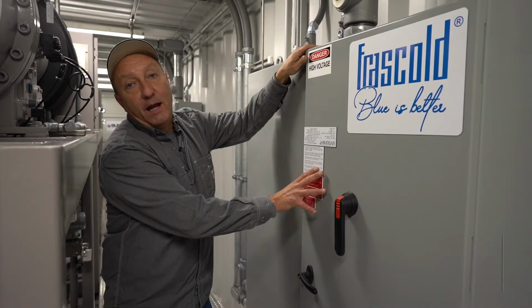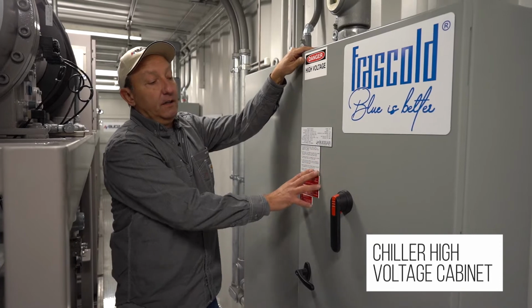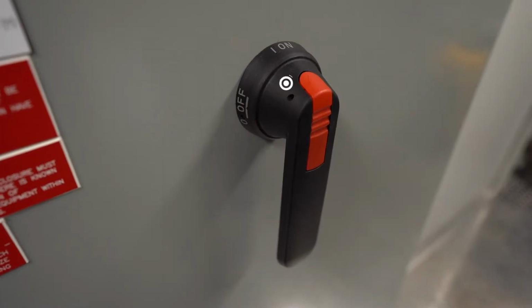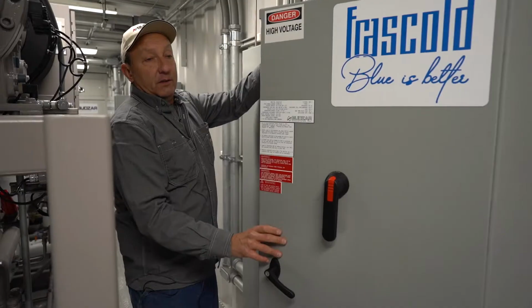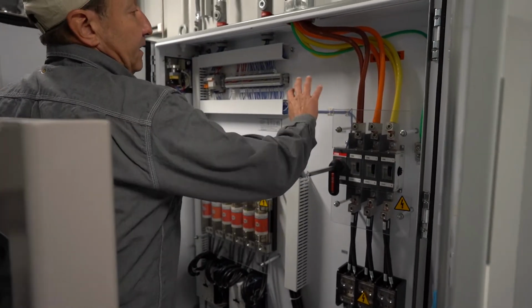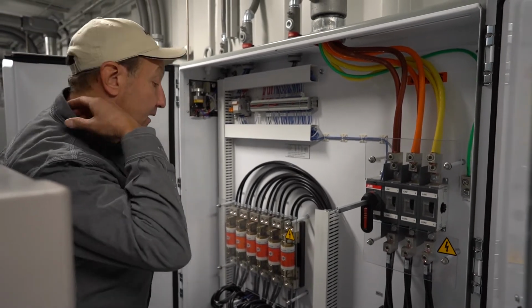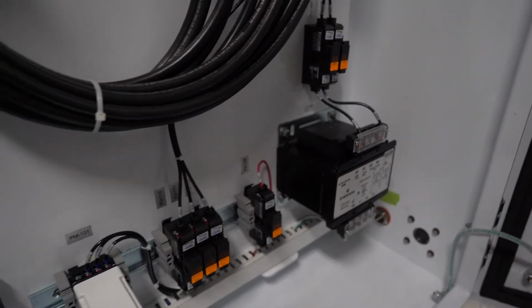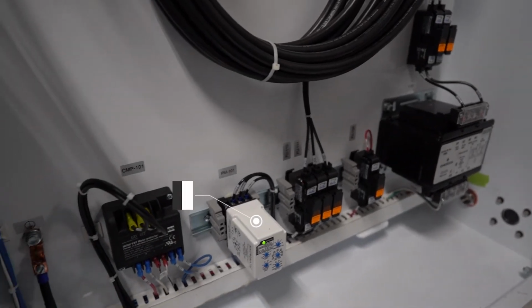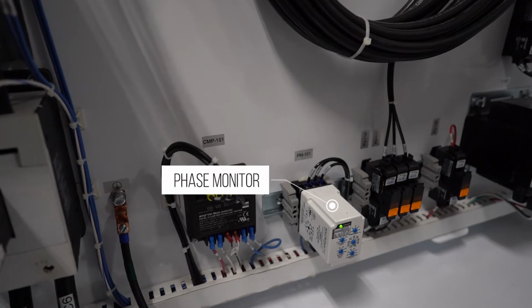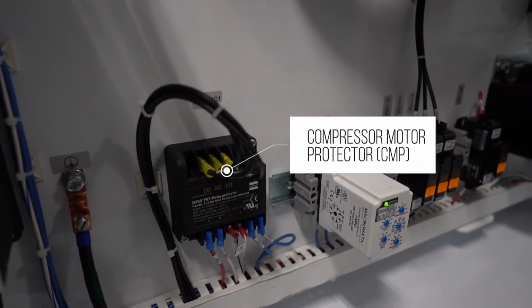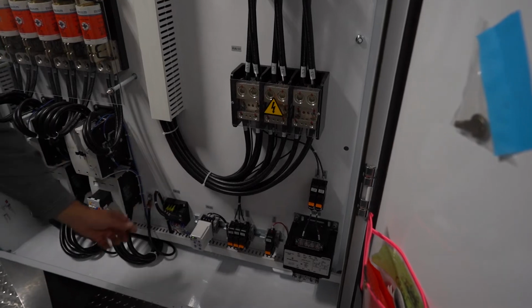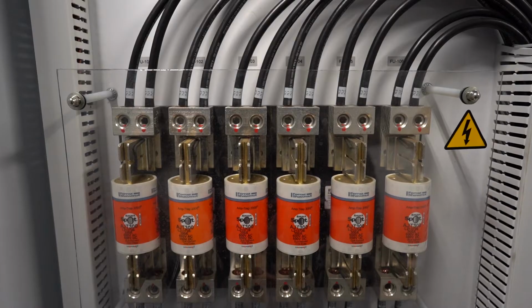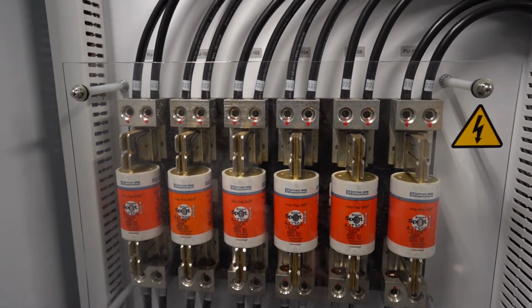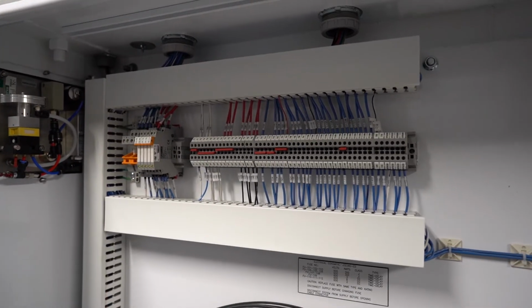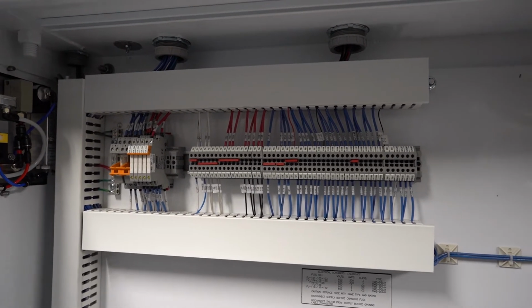This is one of 3 high voltage cabinets for each chiller circuit. Again, has an isolated disconnect handle that's lockable for LOTO. If we open these up, you can see inside, this is our incoming power from the service box outside. We have a 460 to 120 volt transformer. We have our phase monitor. This detects any phase imbalance, the difference between the different legs. And then we have our compressor motor protector, CMP. This is directly related to the screw compressors. The compressors are fuse protected for the 300 horsepower screw Frascold compressors. And then we have a little bit of control wire here that goes to another enclosure we'll touch base on here in a minute.